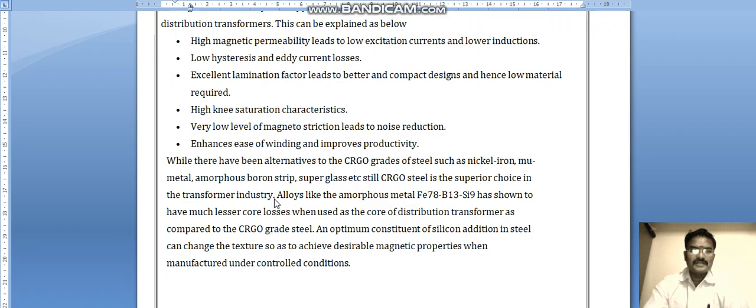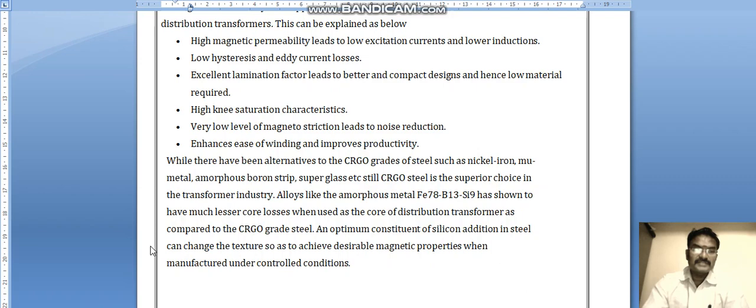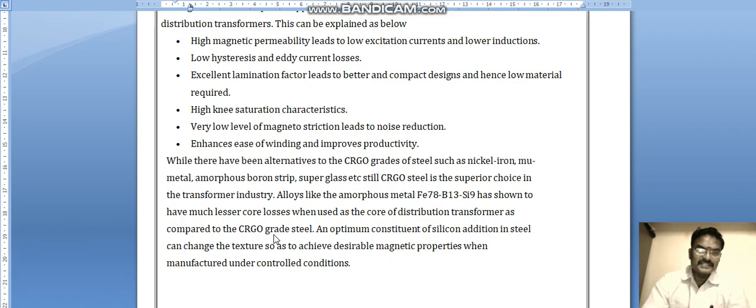While there are alternatives to CRGO grade steel such as nickel iron, amorphous ribbon strips, and superglass, CRGO steel is still the superior choice in the transformer industry. Alloys like amorphous metal Fe78B13Si9 show much lesser core losses in distribution transformers compared to CRGO, but CRGO is still preferred because its cost is lower than amorphous metals. CRGO steel can have its textures changed to achieve desirable magnetic properties under controlled manufacturing conditions.